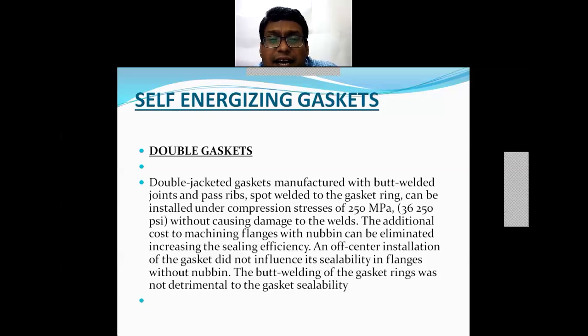These are the double gaskets that will be there, that is double jacketed gaskets manufactured with the butt welded joints and pass ribs, that is spot welded to the gasket ring. They can be installed under the compression stresses without causing the damage to the weld. The additional cost of machining flanges with the nubbin can be eliminated, increasing the sealing efficiency.